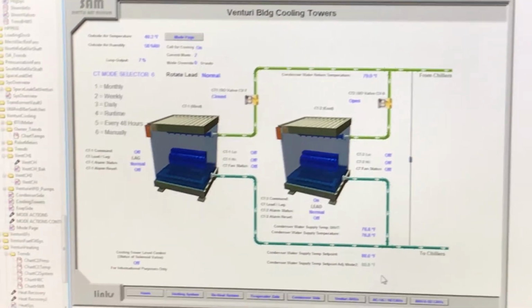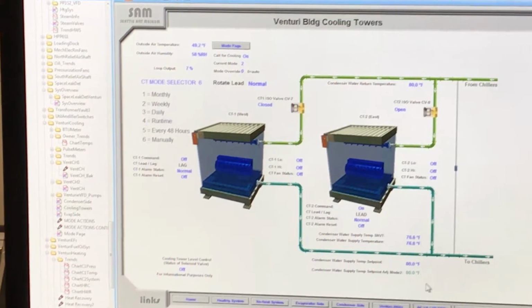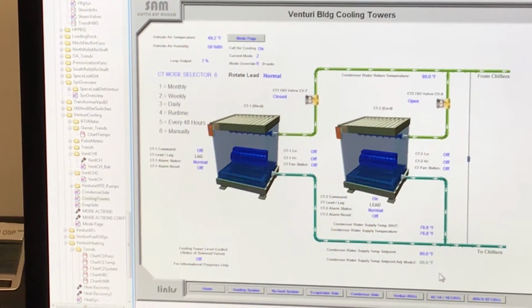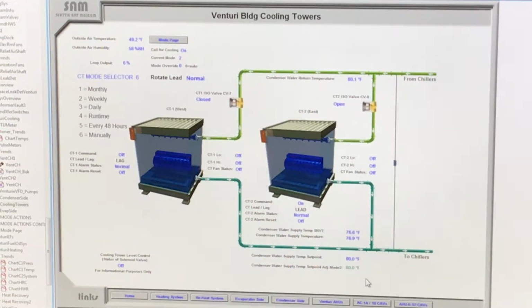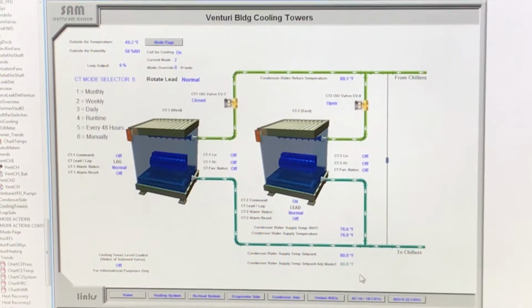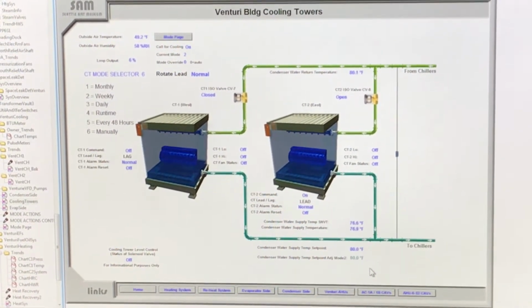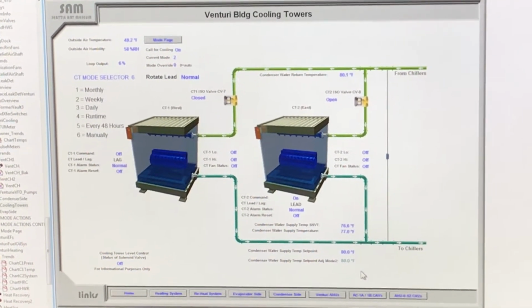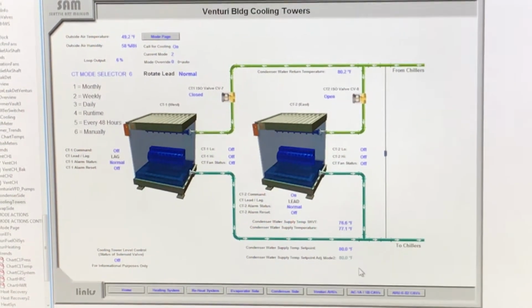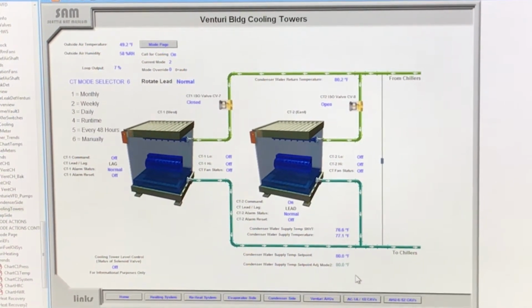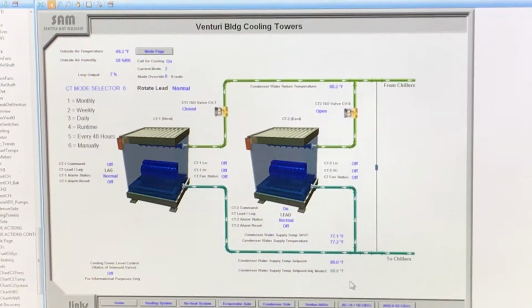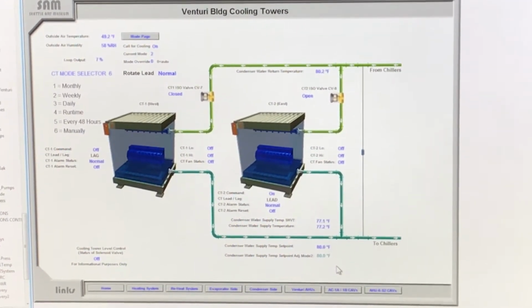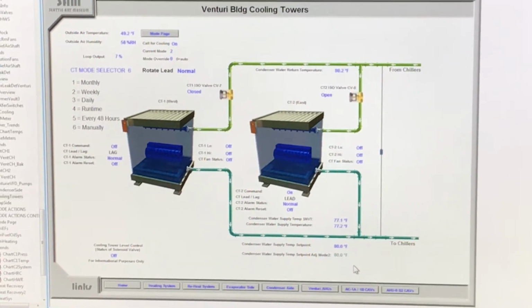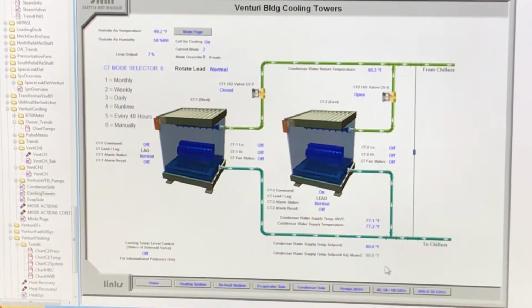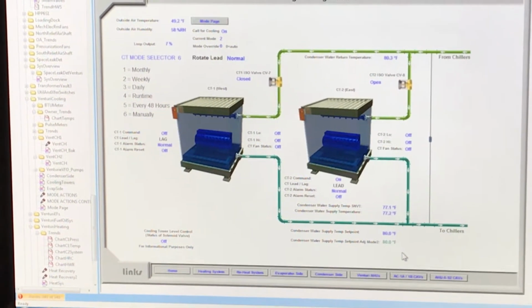But when you are running in heat recovery mode, remember that your entering water temperature to a condenser is usually about 100 degrees. When you're trying to generate heat, the chiller doesn't like too high a temperature. So your loop is designed for 80 to 85 degrees, so that you have about a 10 to 15 degree delta between the cold side and the hot side of the heat exchanger, so that you can actually cool the 100 degree condenser water to a lower temperature.